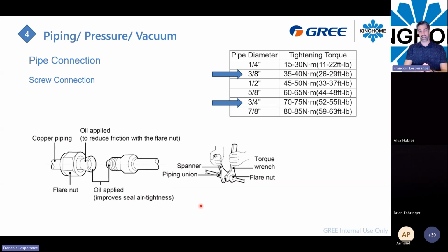Okay, so you will have your connection, and if you go directly through the wall at this point, the thing that can happen is the vibration and all the change of temperature between hot and cold. Because it's a heat pump, it will be very cold outside, then very hot. So the copper will try to expand and retract, and expand and retract. And the weakest point on the connection is your flare.